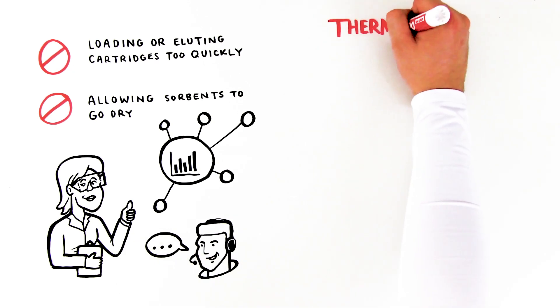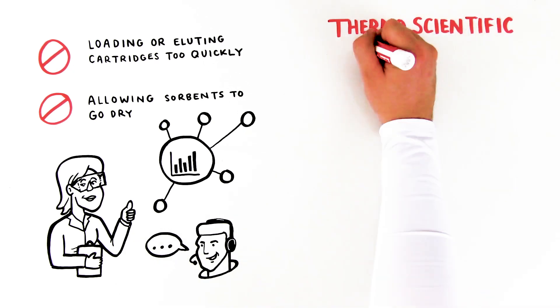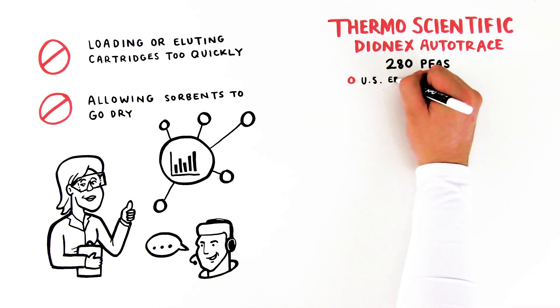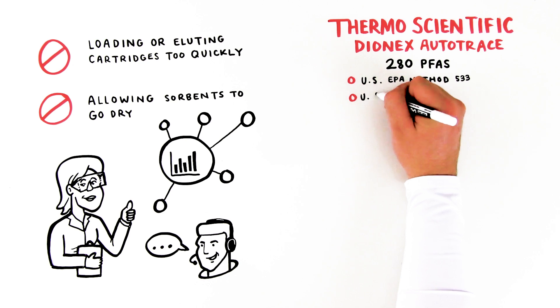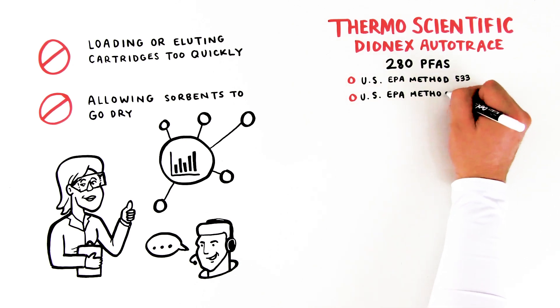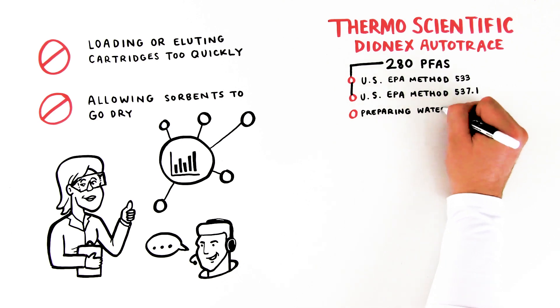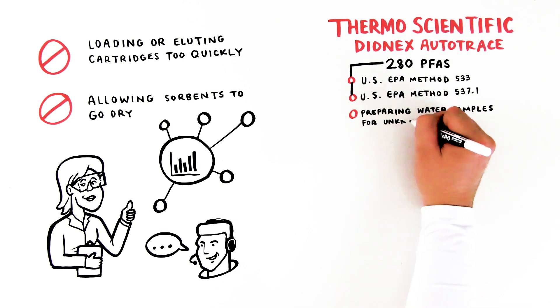Dionex AutoTrace 280 PFAS is designed to automate SPE for US EPA Method 533 and US EPA Method 537.1 or similar PFAS extraction methods. The AutoTrace 280 PFAS can also be used for preparing water samples for the discovery of unknown PFAS.